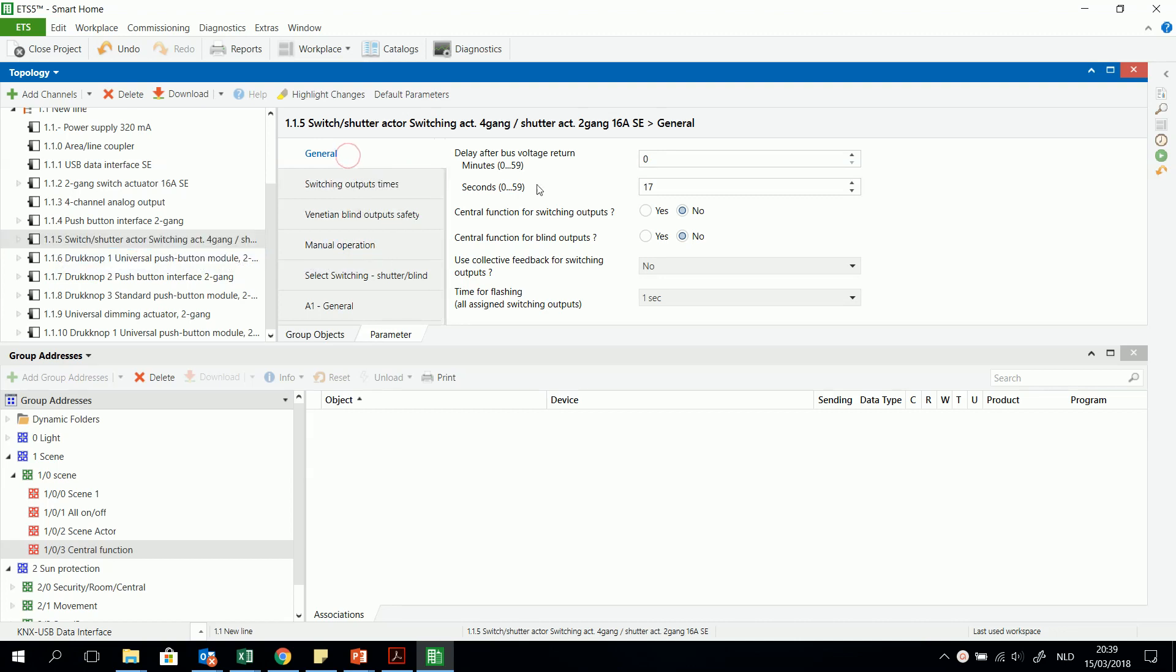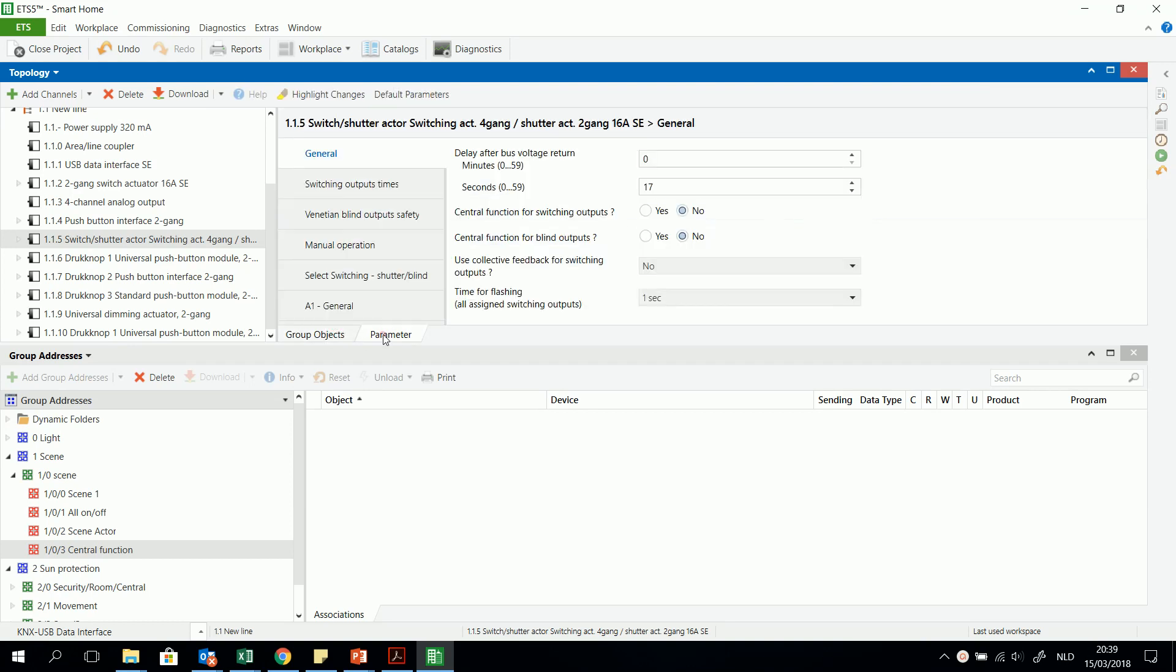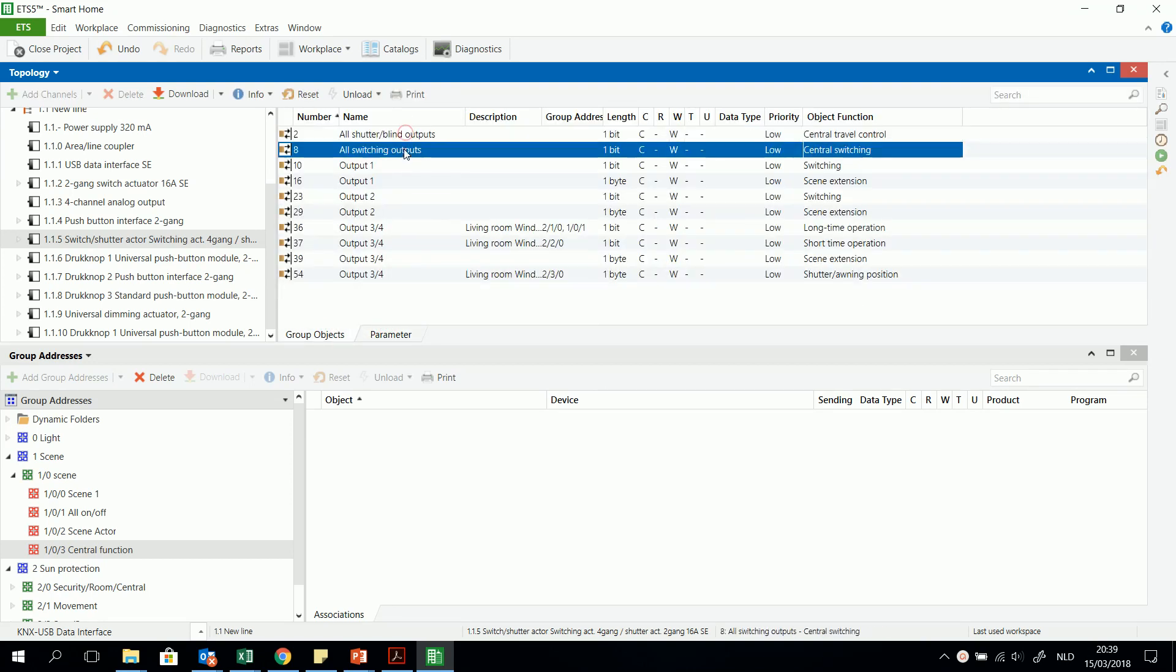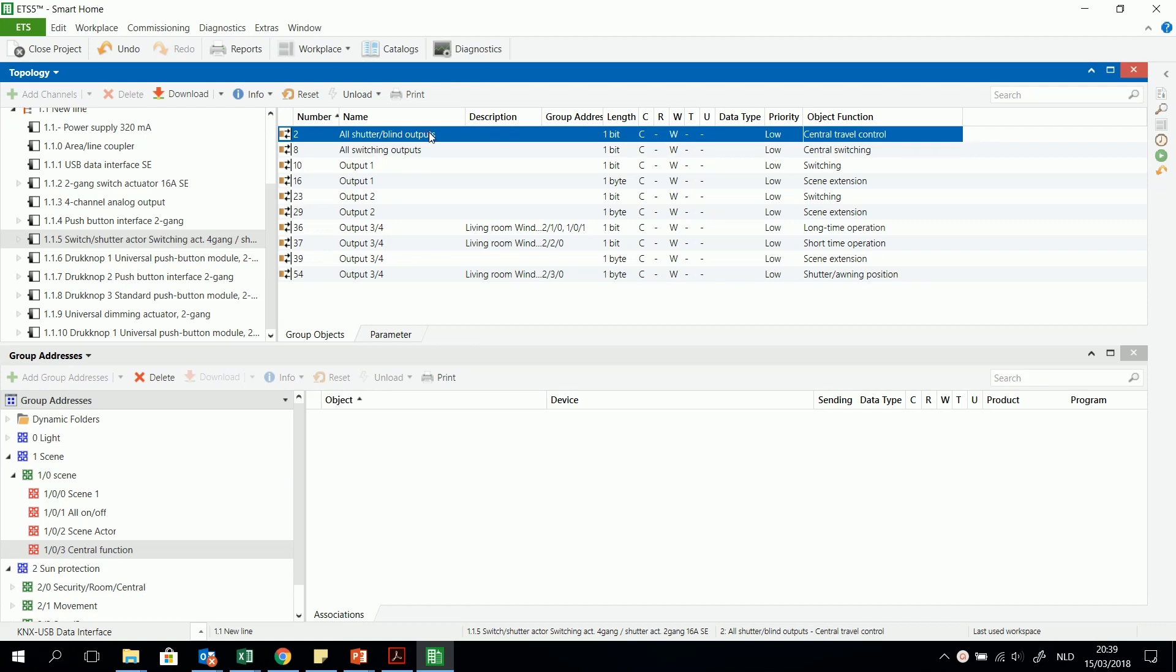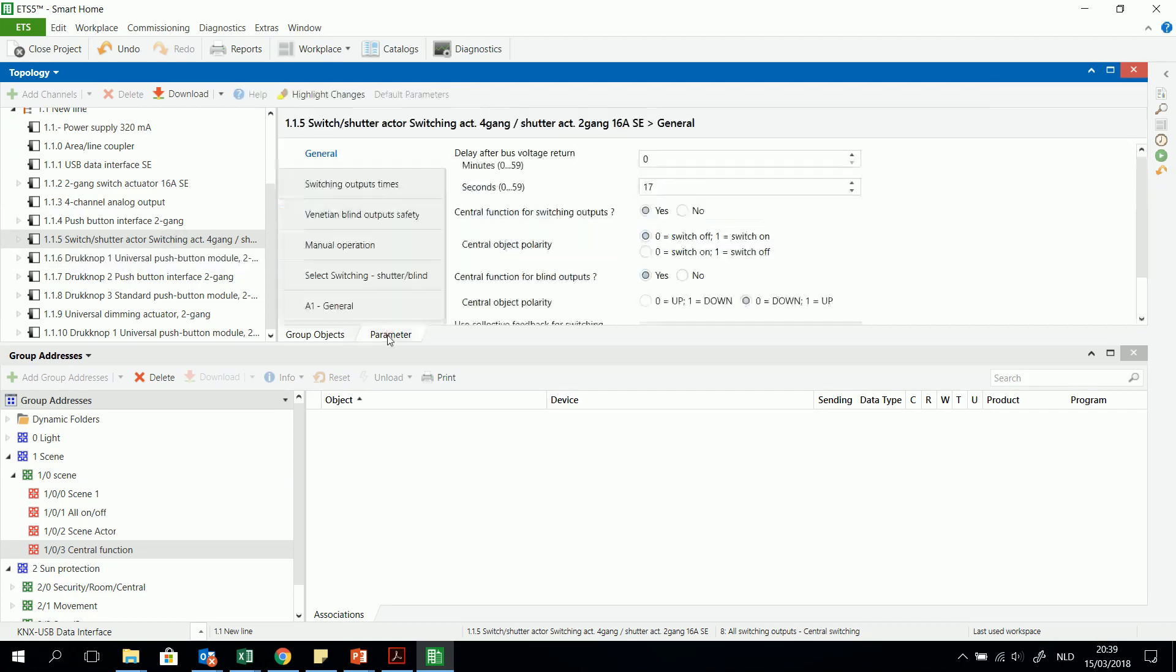In the general parameters I see central function for switching outputs and central function for blind outputs. So take a look at the objects. For the moment there are no central function objects. When I click yes you will find two central traveling control central switching objects of one bit. This is one for the shutters, this is the other for the switching outputs, because it is a combination of a switching and shutter actuator.